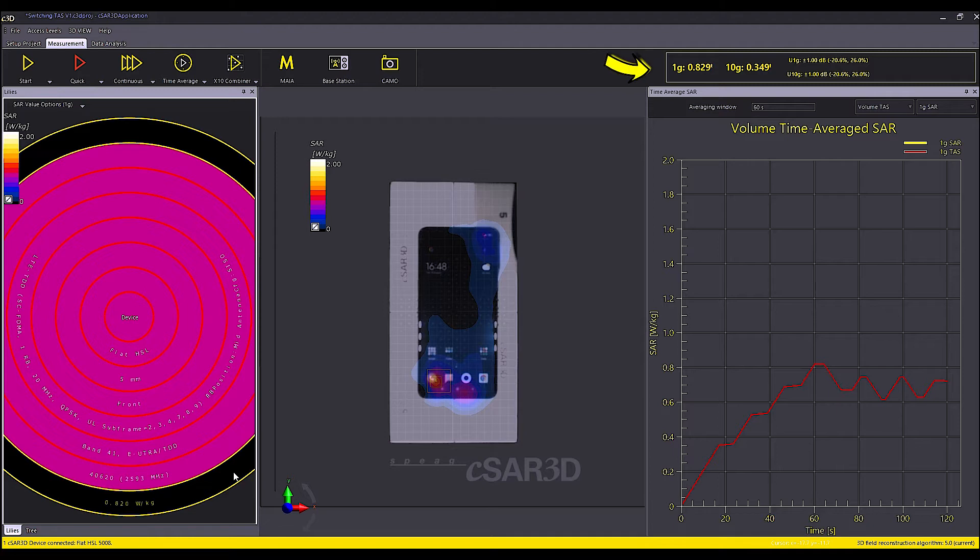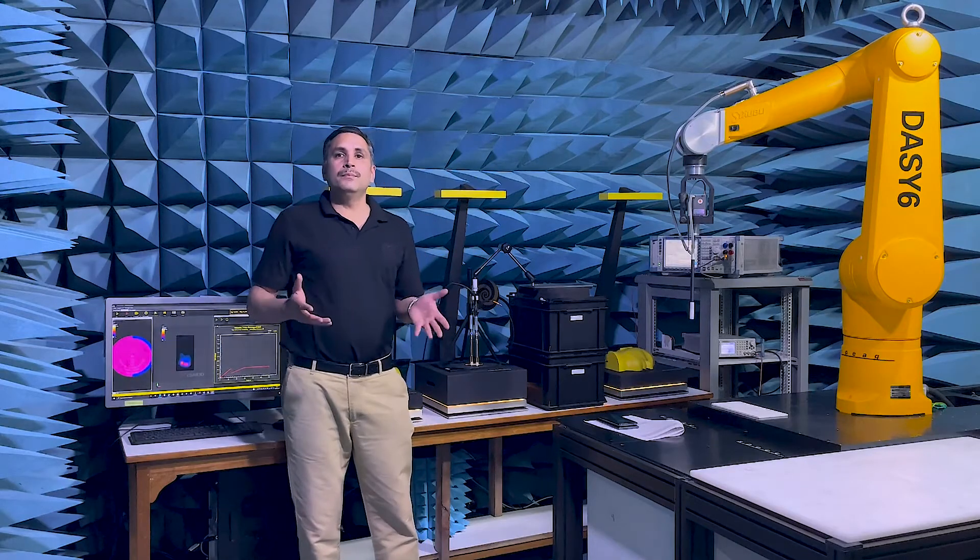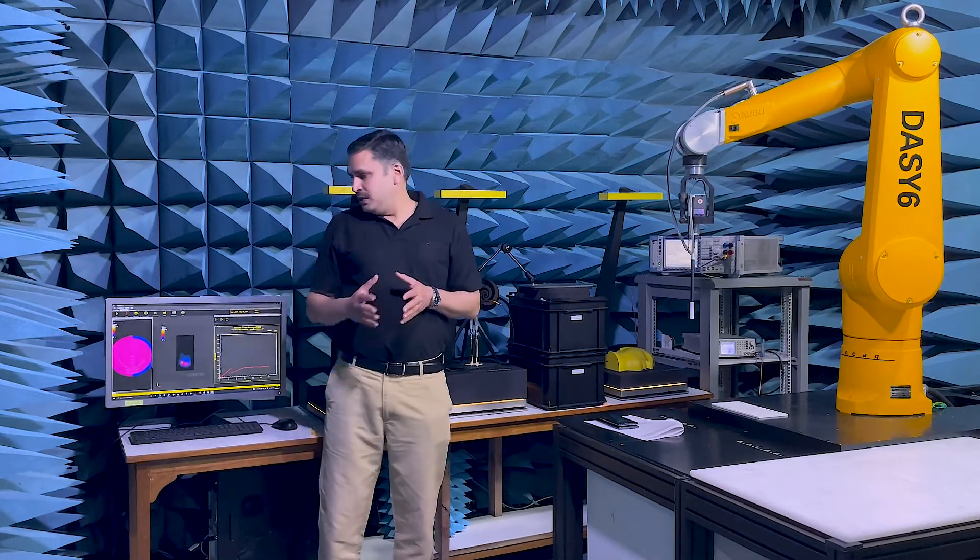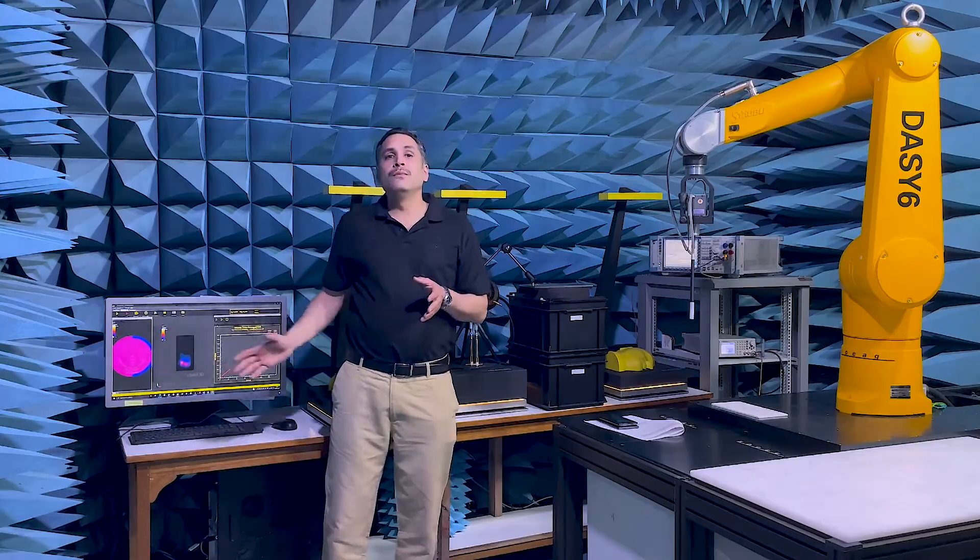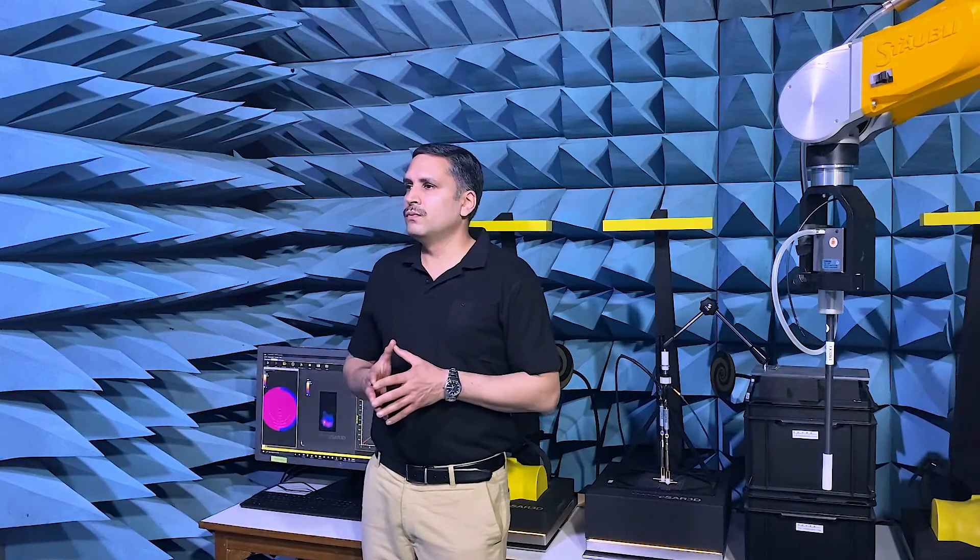the resulting peak spatial SAR is now 0.829 Watt per kg which is 1.3 dB below the value obtained by the PSAR mode. This is really impressive and the feature itself is extremely easy to use.